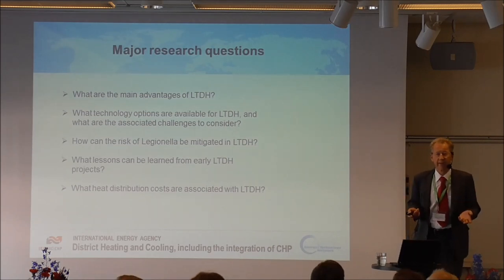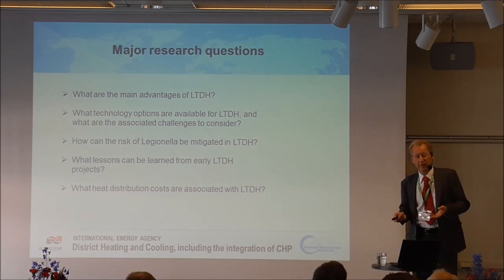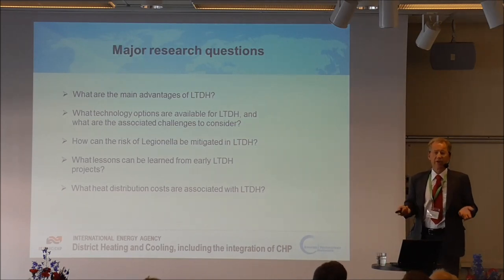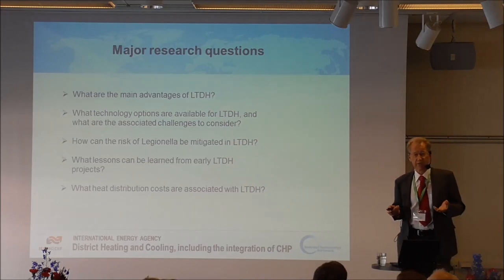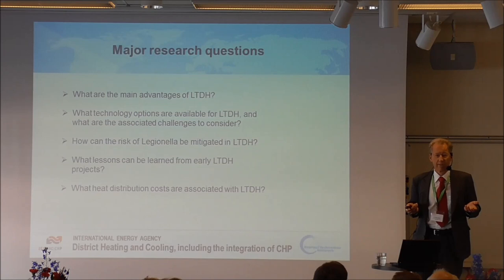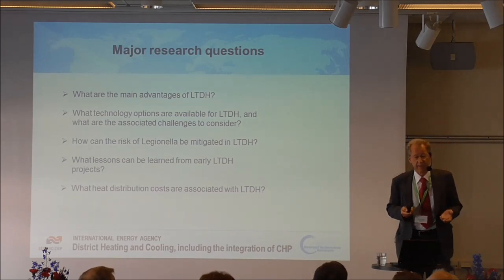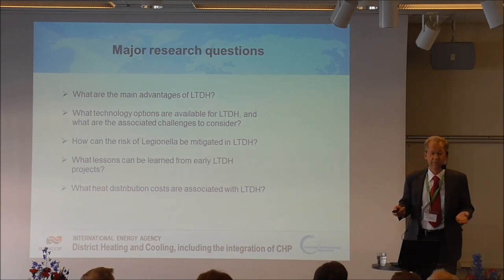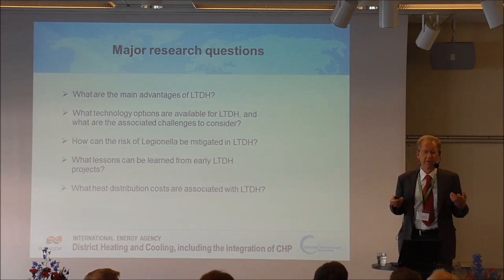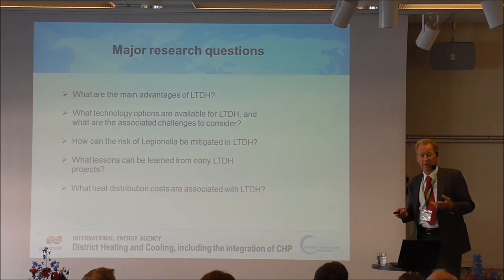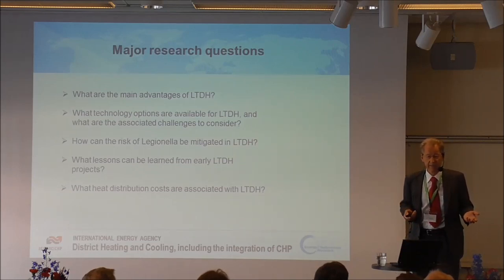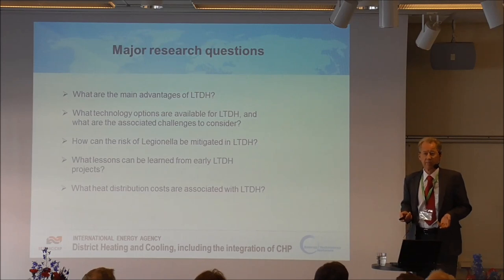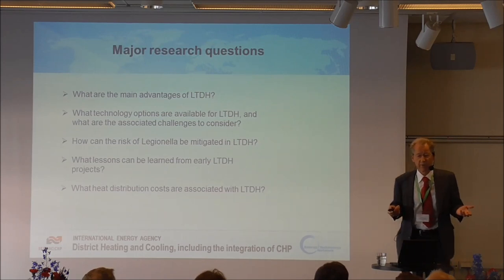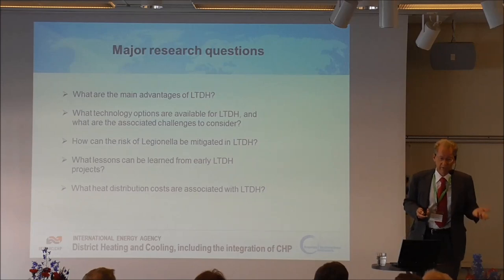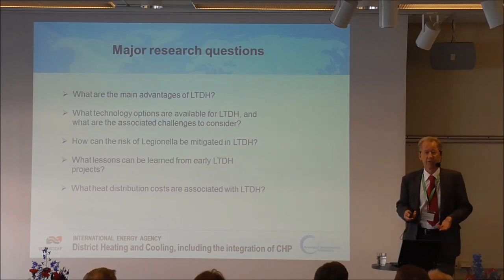So we can offer a solution which is probably much more secure in real operation. Local production of domestic hot water in a flat heat exchanger, every flat. And that's the way we can make use of low temperatures, because then we don't need to have 50 degrees, 55 degrees, 60 degrees, depending on what is the local requirements. If you have a system without a tank, you can use the 40 degree hot water, which is what you need for comfort. So that's an example of combining security concerning the Legionella and benefit for the performance of the system.